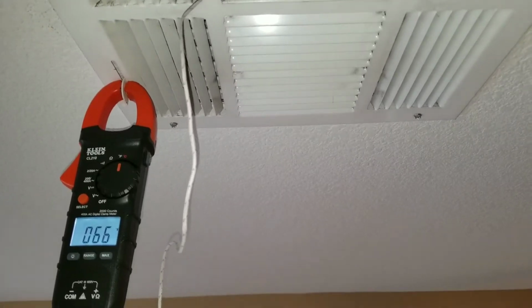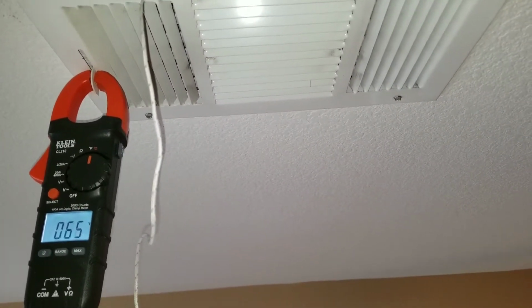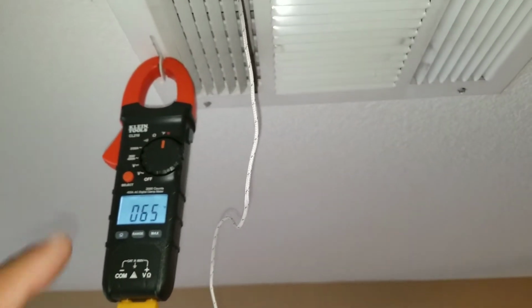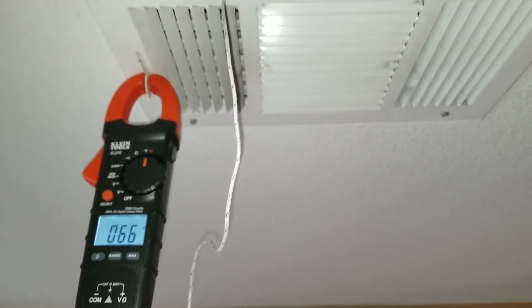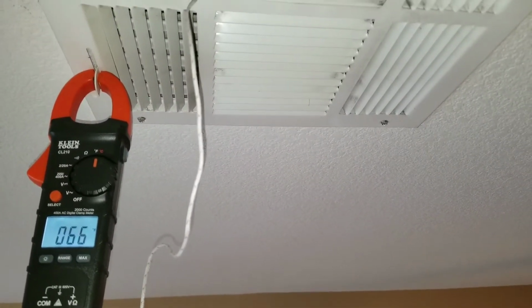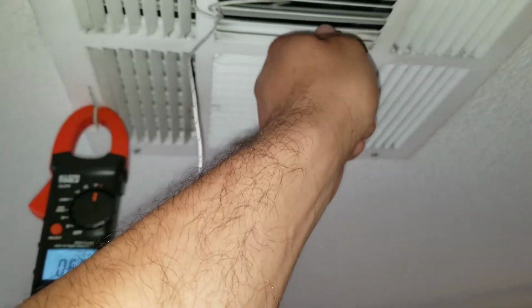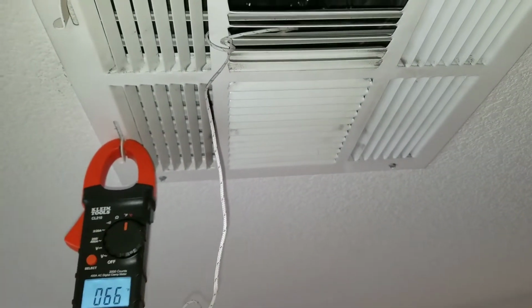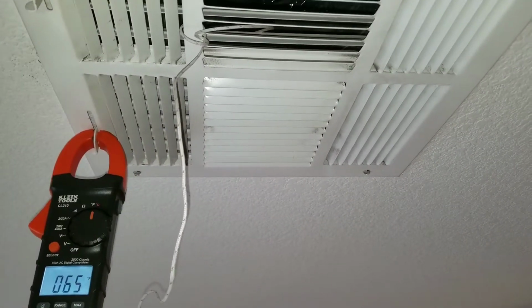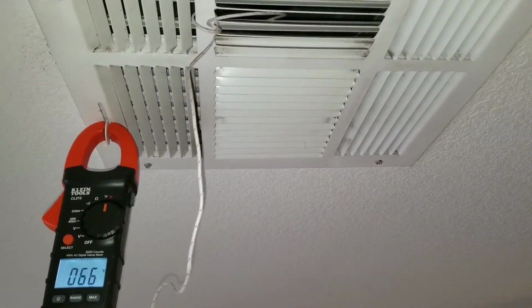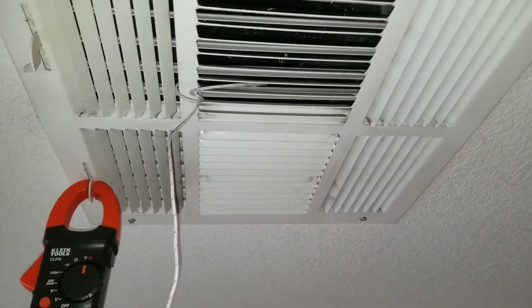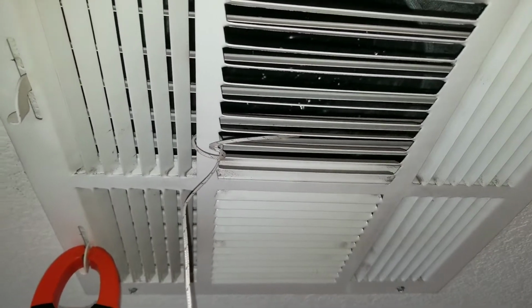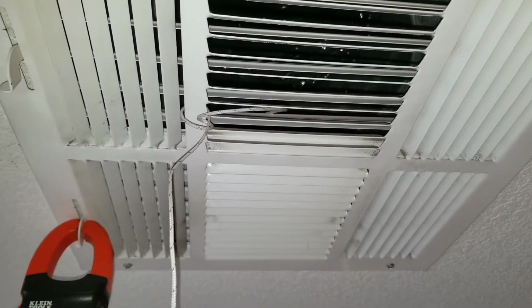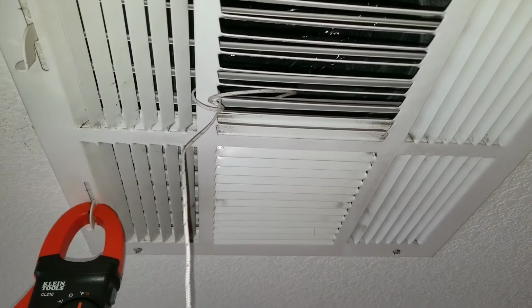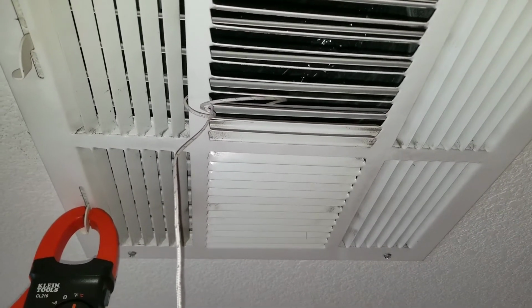So if you're going to take a reading of the ambient air at your vent or at the return, the one tool that is more efficient and effective and made for that specific purpose is going to be the temp probe from your multimeter. If you don't have a multimeter, you can buy those little pocket thermometers and just sit it up there. As long as it's picking up the actual temperature of the air that's coming out, or the ambient air, that's what you're trying to account for whenever you're using your superheat or subcool method, especially when you're dealing with not only the temperature inside of the house, but also at the evaporator coil and the condensing unit. And then you want to factor in the ambient air, what the temperature is outside.